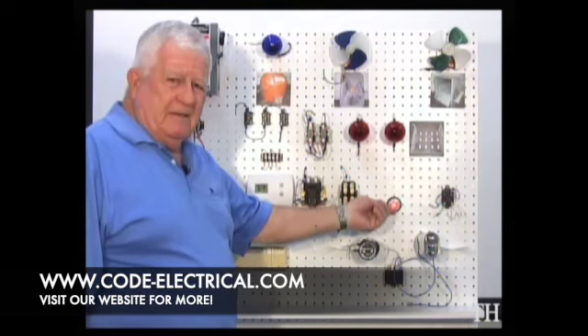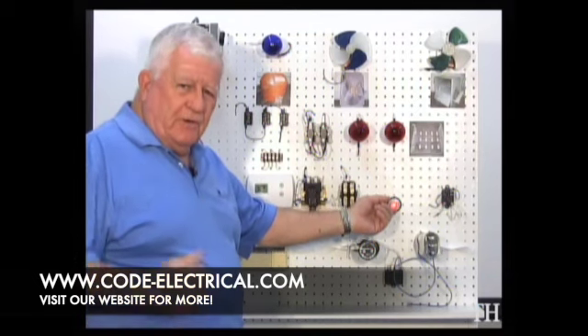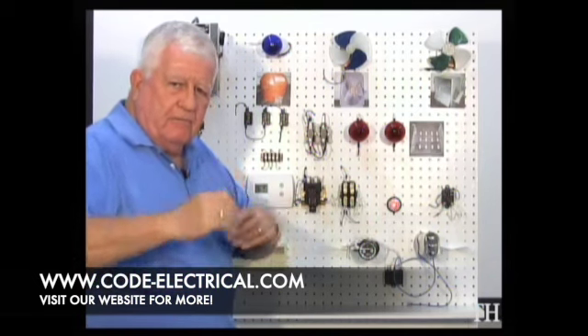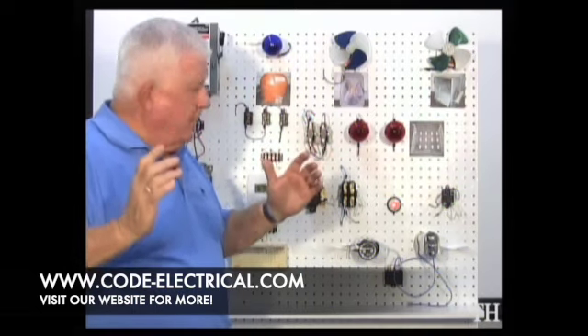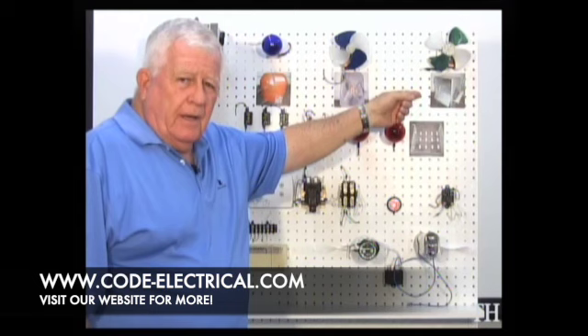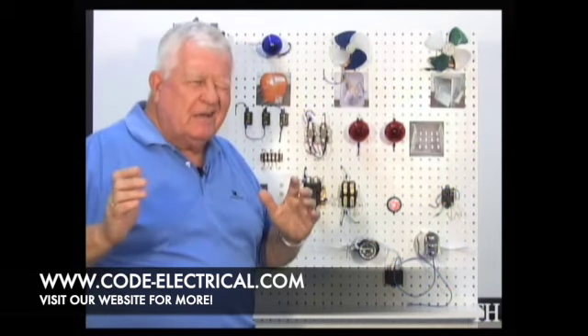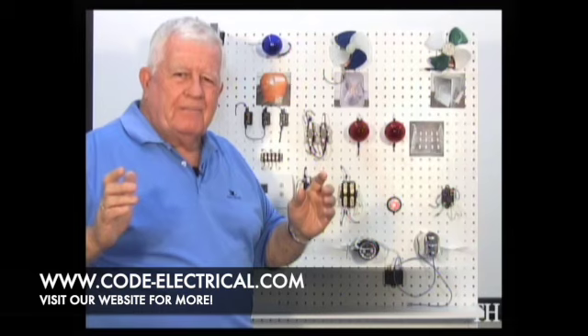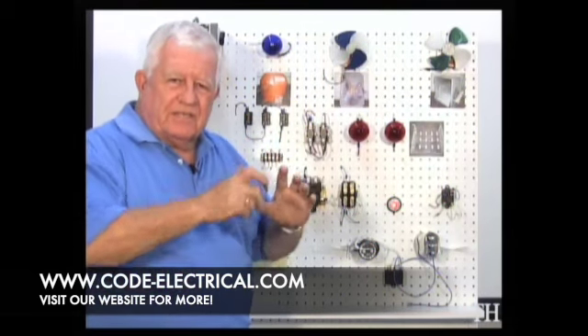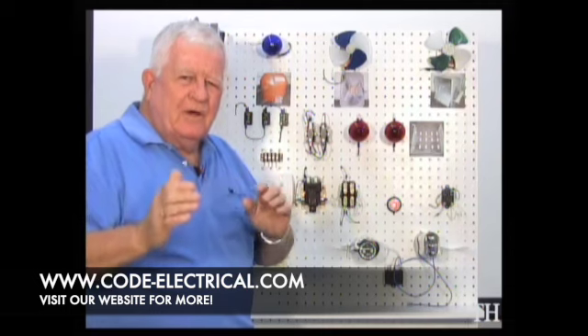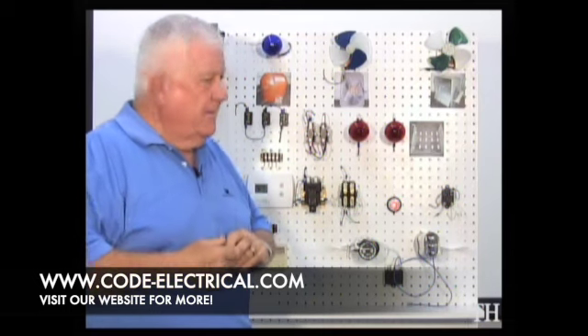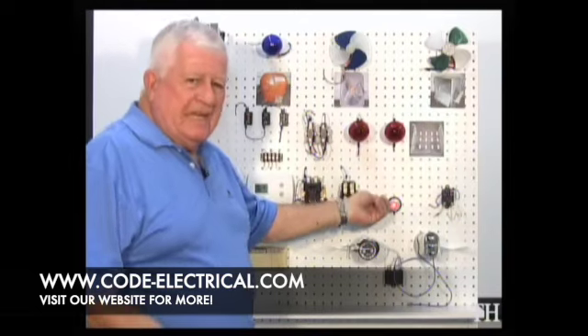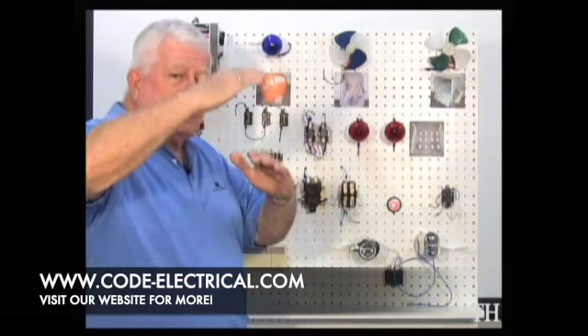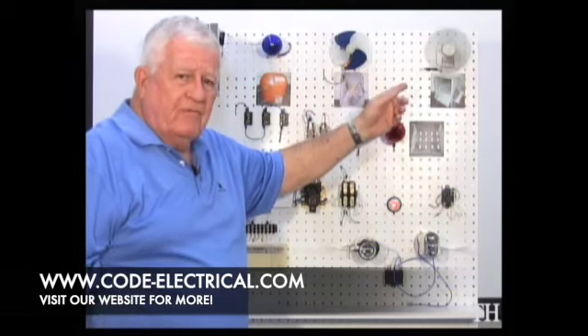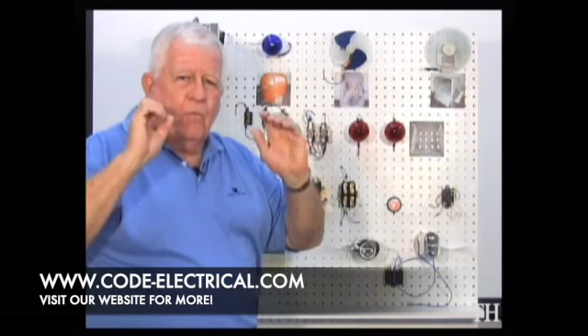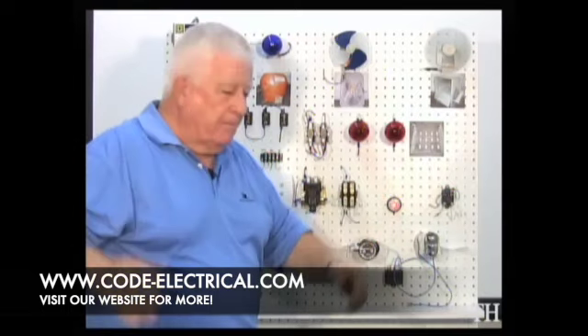When I flip it to heat, I've sent a signal to that gas solenoid to energize and let the gas out, the igniter fires it, and the heat exchanger warms up. This fan won't come on until the heat exchanger reaches about 90 degrees Fahrenheit - there's a temperature switch you can set, but generally it's around 90 to 100, because I don't want to blow cool air through the house. So as the heat exchanger warms up and reaches that temperature, wham, the fan comes on, blowing warm air through the house to heat it up.